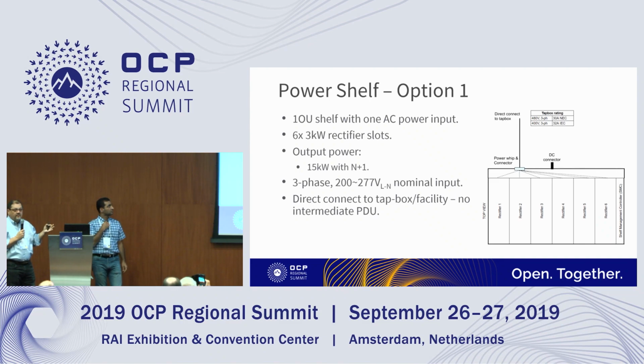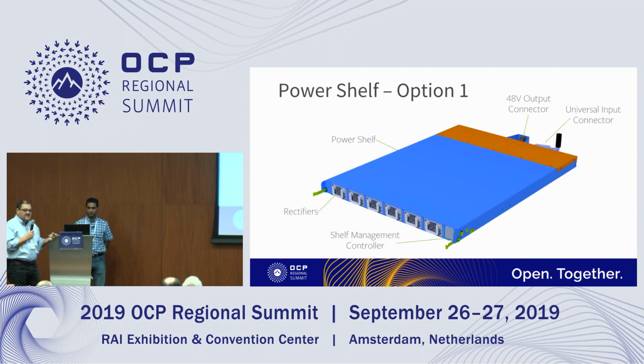So 3 basic options based upon that 3 kilowatt rectifier. Option 1 is an N+1 available system. 6 power supplies, 3 kilowatts, 15 kilowatt type of applications. 1U, it is using the newly developed 7-wire connection. Again, wide range input, 200 to 277. No breakers in the box, direct connection to the overhead whip, no PDUs in the system. We're simplifying that. This is a representation of what the system will probably look like. You can see on the left side 6 power supplies and an SMC controller. On the back side, you have the 48 volt connector as well as the universal power connection.